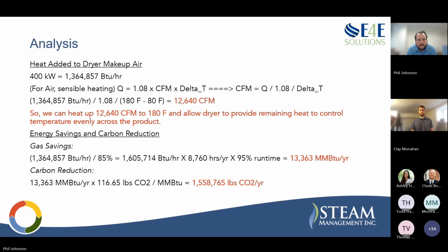So doing a similar calculation, we work out that this could preheat a little over 12,000 CFM of air. If the airflow needed for that dryer is close to that value, then we could preheat it all to 180, or if the flow is much higher than that, then we would just preheat it to a lower temperature, and then the gas burner in the dryer would do the remainder of the heating.